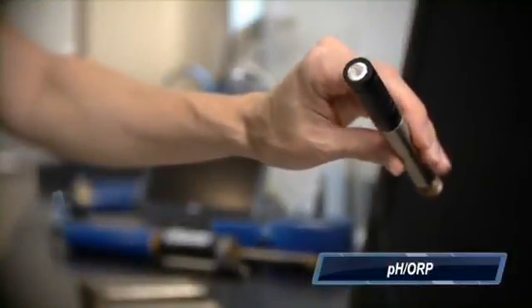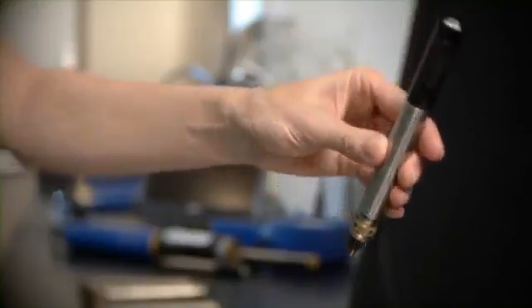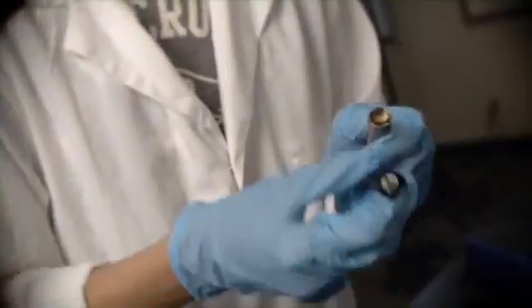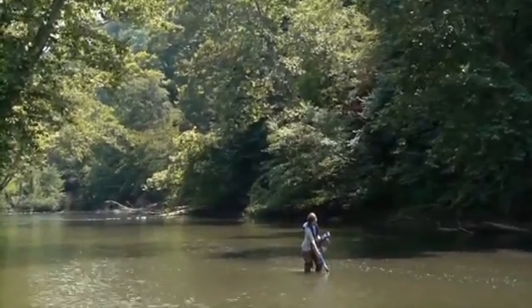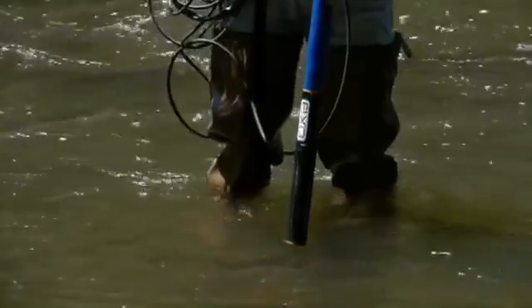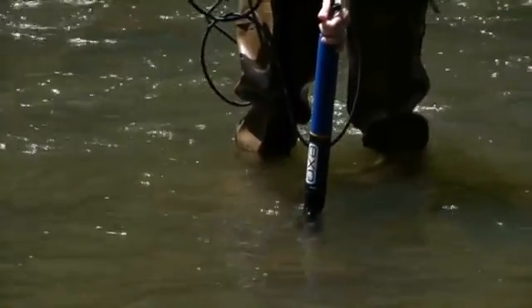pH/ORP. We've introduced a modular design to the pH/ORP probe. Once a probe's electrolytes become exhausted over time, you can simply replace the probe's tip, saving time and money. Not only will this represent a decrease in operating cost, but the pH/ORP probe is now more accurate and responds faster than previous versions and works well in conditions such as cold and low ionic strength waters.